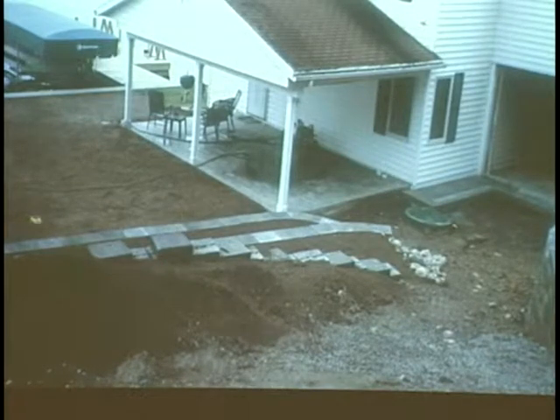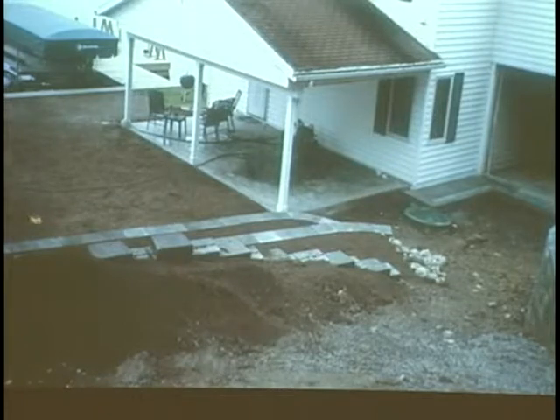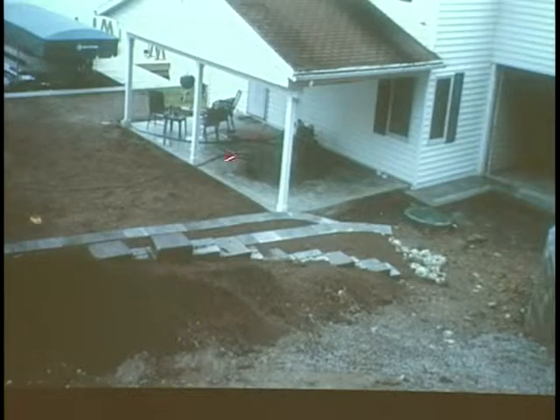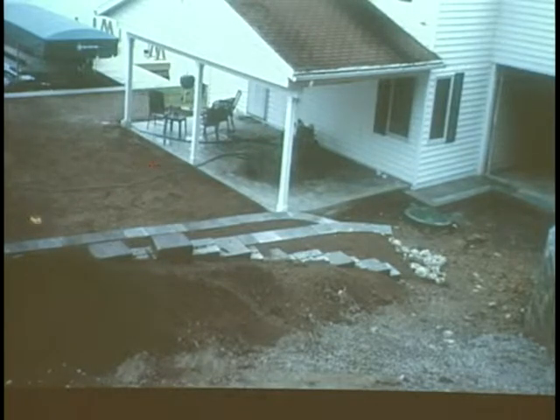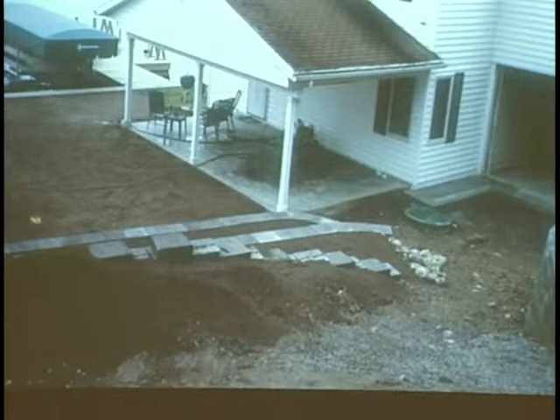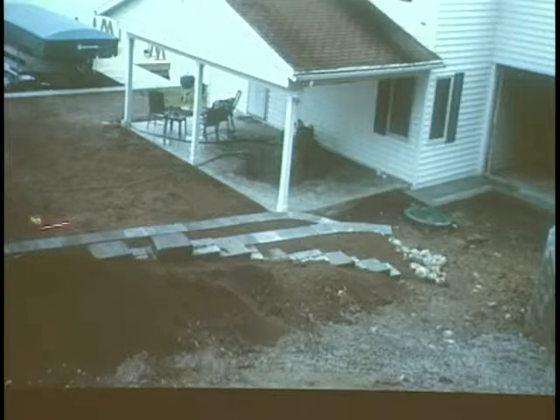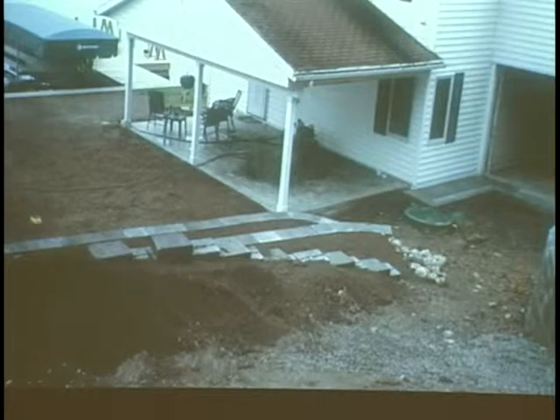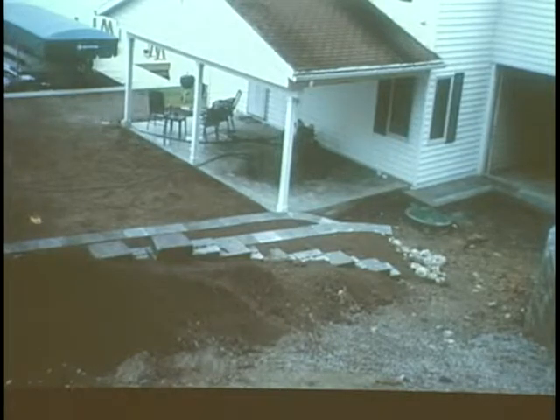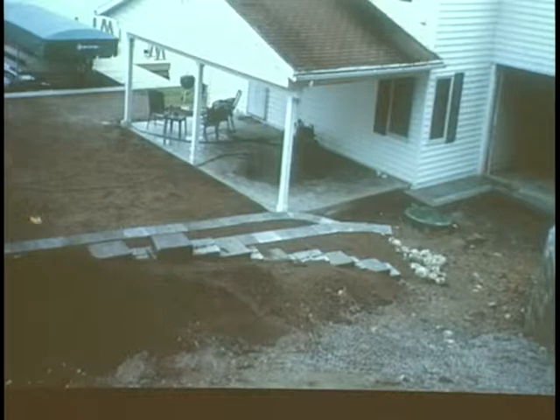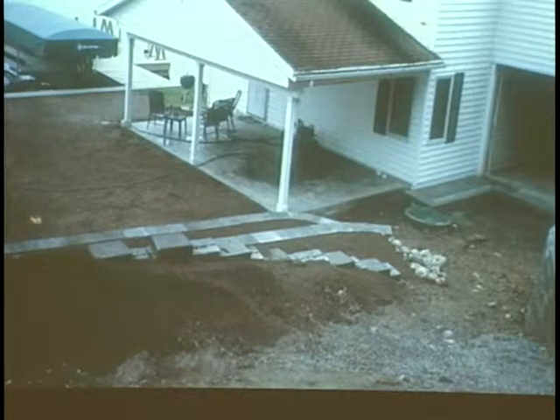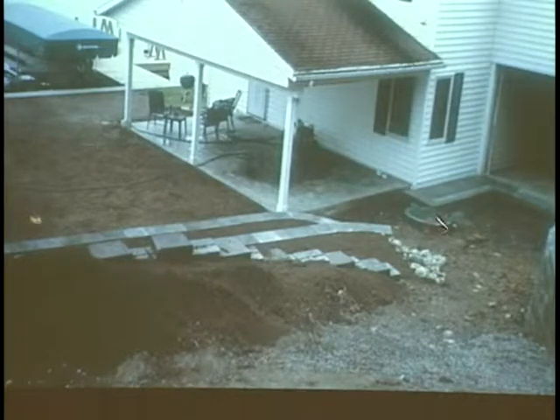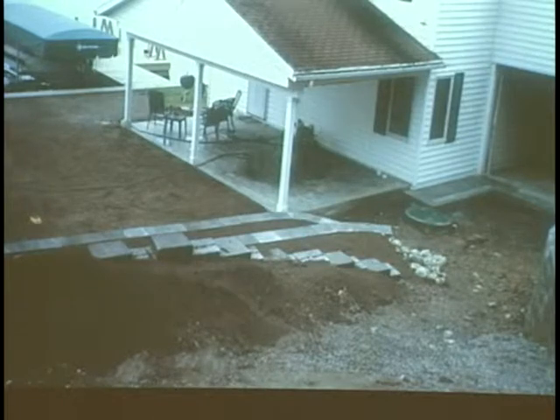Here's a situation where, prior to DEC oversight, this area got filled in and this place was built back in the 50s or 60s. They had a steel septic tank and leach lines in the fill area. The steel septic tank rusted out and caved in. The owner said we'll just send a new septic tank and tie in, and I said no. You're in fill area here with the lake right there. Our policy is: failed system, the repair is going to meet current health department standards as best as possible. We could not get 100 feet away from the lake, so instead we put another aerobic treatment unit in and pumped up into this cribbing area.